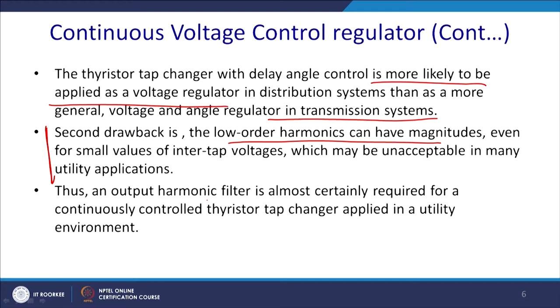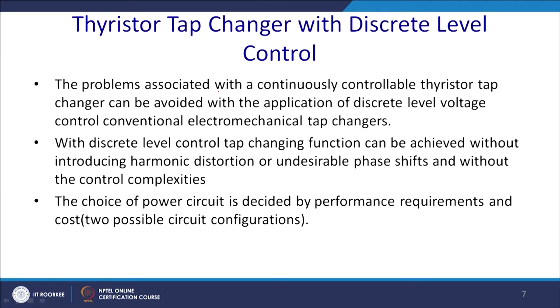An output harmonic filter is almost certainly required for a continuously controlled thyristor tap changer applied to the utility environment. That adds extra cost to the system. The problem associated with a continuously controlled thyristor tap changer can be avoided with the application of discrete level voltage control, the conventional electromechanical tap changer that we will see now. With discrete level control, the tap changing function can be achieved without introducing harmonic distortion or undesirable phase shift, and without any control complexity. So, it is just a mechanical tap changer.